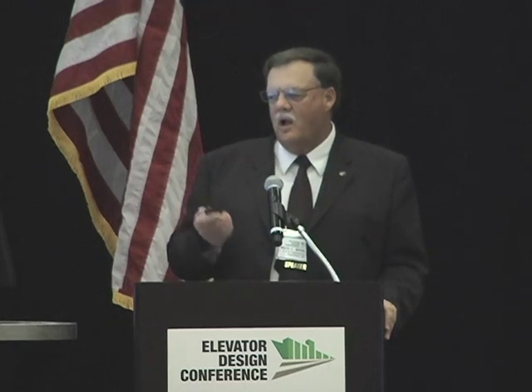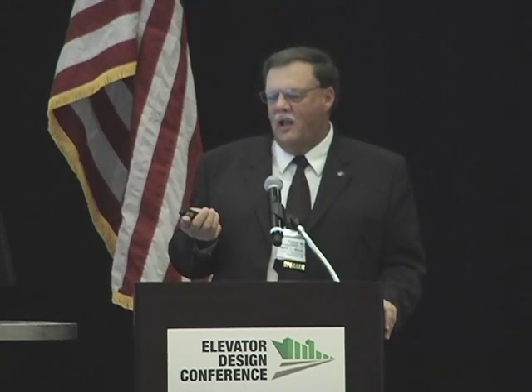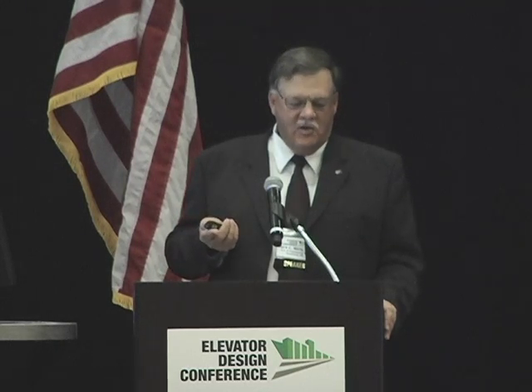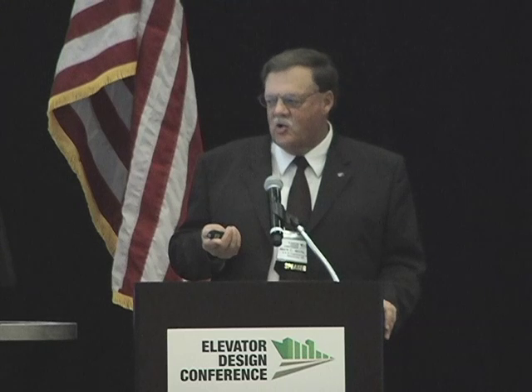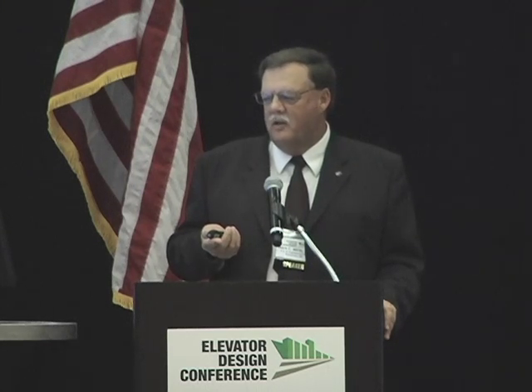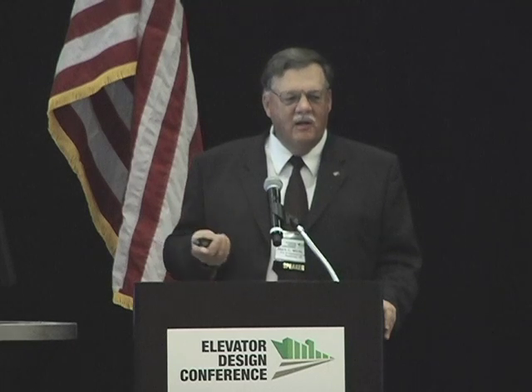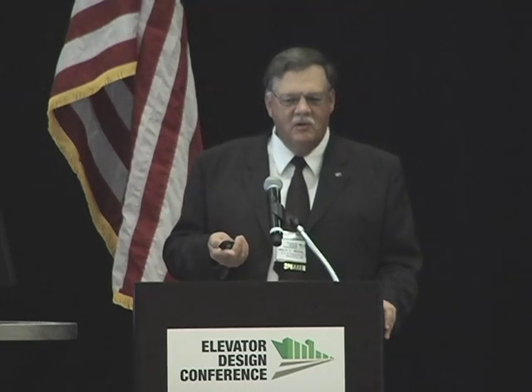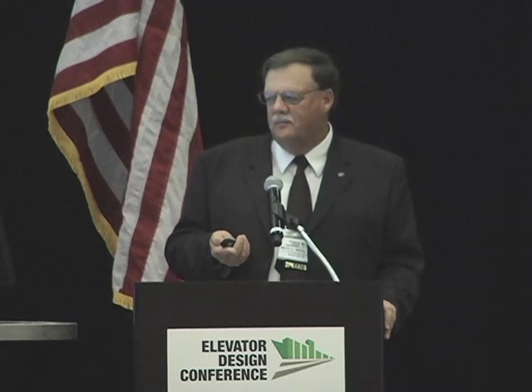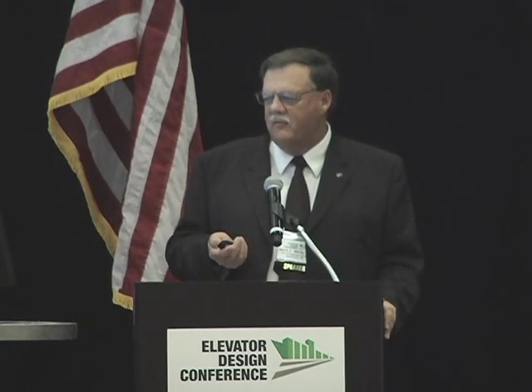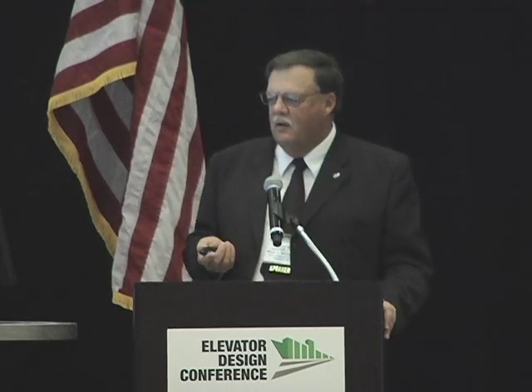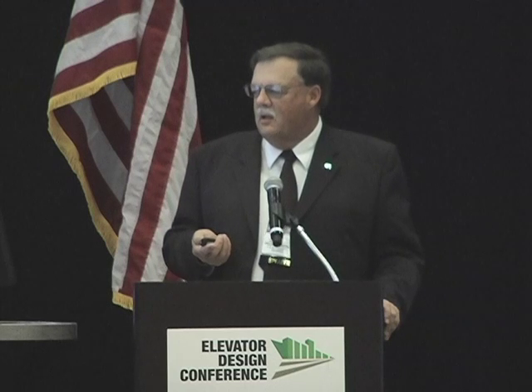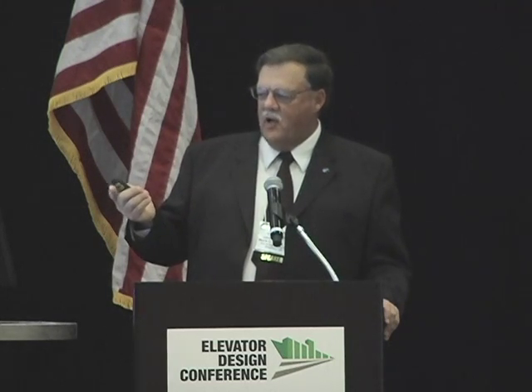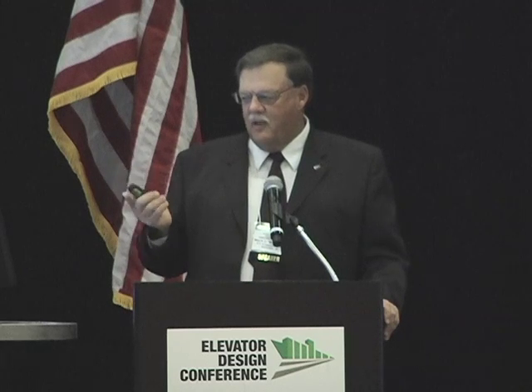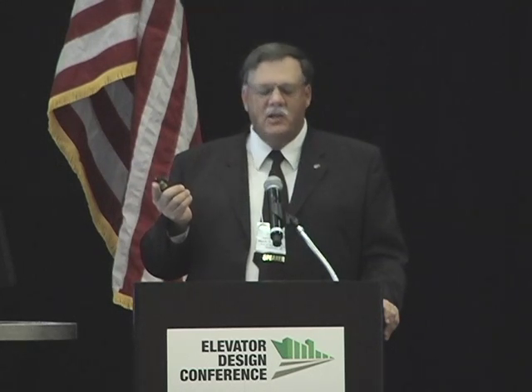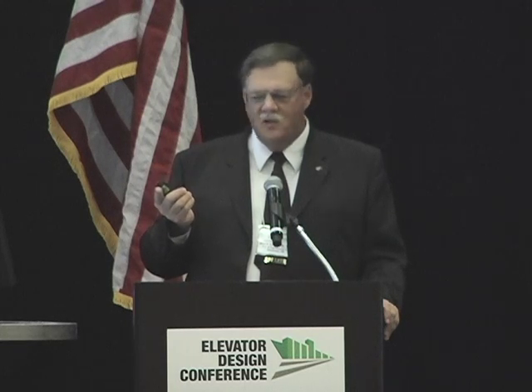And then we have a lot of new equipment now that is designed as arc resistant, with all the things going on with arc flash safety and protection. The manufacturers have come up with entire designs of equipment specially built with arc resistant features for safety, to reduce your maintenance requirements and increase your arc flash safety. Here's another piece of equipment from Siemens, and here's an example of their equipment. And you'll see they actually have venting in the top of the equipment, and most of these companies have complete presentations on how they design this equipment.